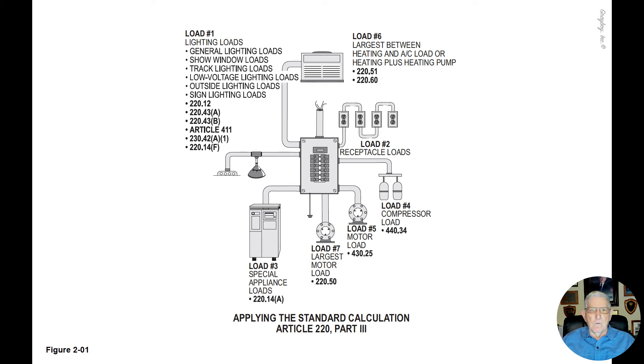Dealing with load six, you choose the largest between the heat or the air conditioning load, and you drop the smaller load in accordance with 220.60, 220.51, and so forth.